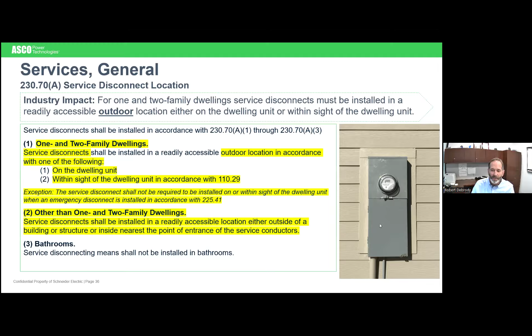So another way that they've deemed necessary, they really want to be able to find that service disconnect. So what they're mandating now, that on 1 and 2 family homes, that you will have the outside of that enclosure clearly marked in a red label with white lettering saying this is where your emergency disconnect is. And then once you open up that cover, right next to that disconnect switch, you will have another notification that says this is your service disconnect. So trying to make things very clear for anybody arriving to a 1 or 2 family home.